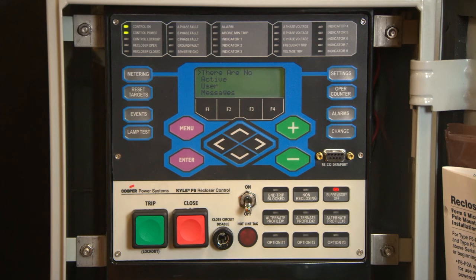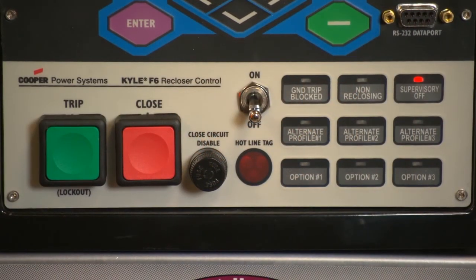Note: when the close circuit disable fuse is removed, the trip circuit remains active and will trip per the programmed time current curve for a faulted condition. Important: if the close button is pressed after the close circuit disable fuse is removed, do not reinstall the fuse until after the alarm LED illuminates within approximately 5 seconds to indicate close malfunction. Reinstalling the close circuit disable fuse prior to the close malfunction alarm indication will cause the control to close the recloser.